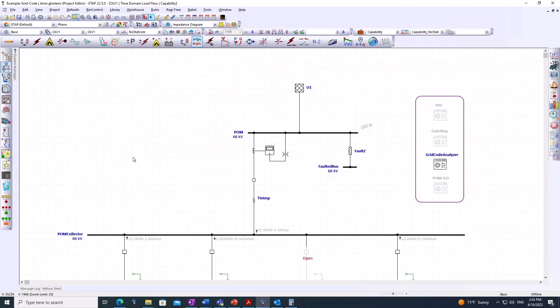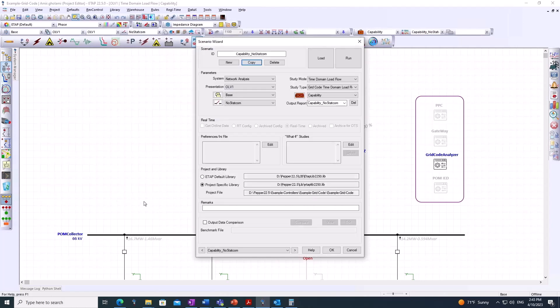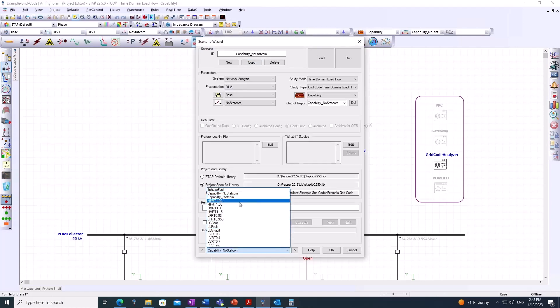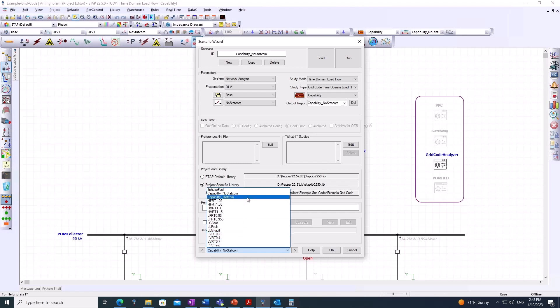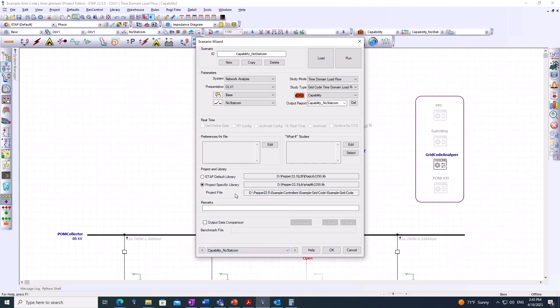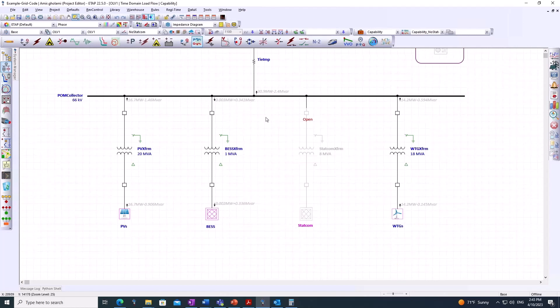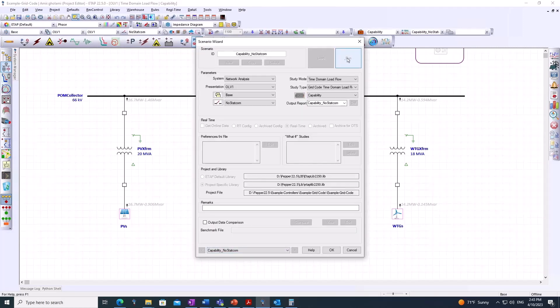In this example grid code project, going into the scenario wizard, there are multiple scenarios already defined, all of which address the grid code studies. Starting with the 'capability no STATCOM' scenario: once loaded, the STATCOM is put out of service. The purpose of this study is to define what impact the STATCOM has and how the grid code requirement can be met by adding extra reactive power support to the system.